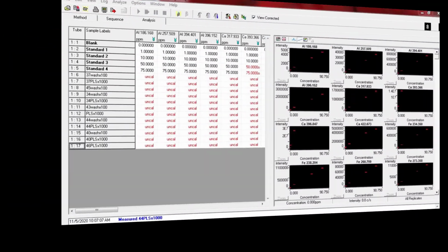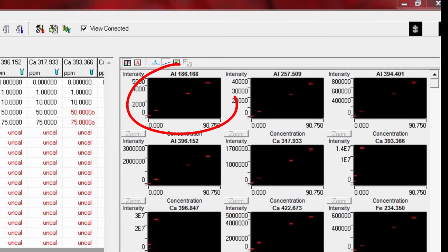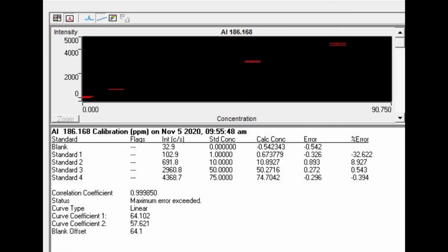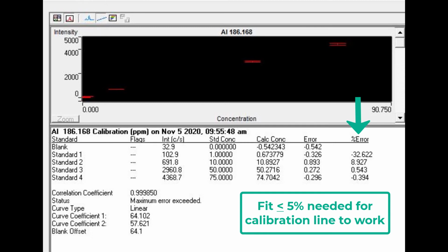Let's take a closer look at the aluminum wavelength 186.168 by double left-clicking on the black box. The window that pops up displays the standards that are included in the calibration calculation, the measured intensity, the concentration you think that you prepared, and the actual measured concentration, along with the error. If a calibration line is drawn and any point has an error greater than the default of 5%, the fit will not be seen in this window.